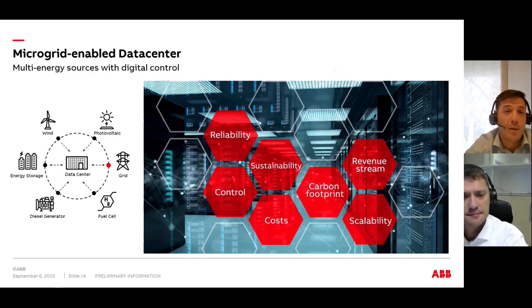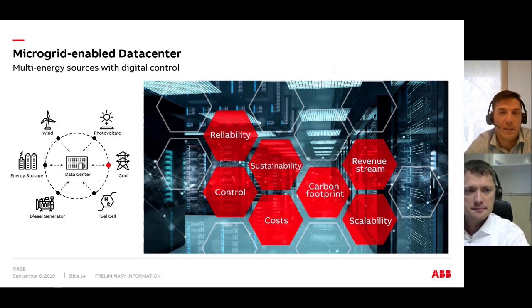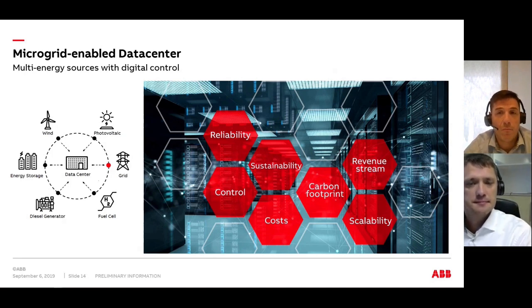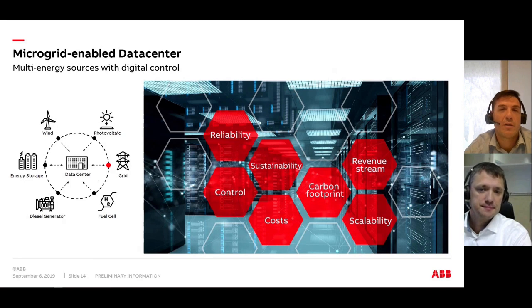This is not the target if we consider the previous point on sustainability. When we have a BESS in the microgrid, we have renewables. We can participate in different monetization schemes for additional revenue streams or even cost savings. These are possible due to the versatility of the microgrid for data centers, either by additional streams or by cost cutting. The return on investment of a microgrid-enabled data center can be readily realized. Grid services can be easily provided by just having a battery energy storage within the microgrid concept, in terms of reactive power support and fast frequency reserves. This is going to automatically enable an additional revenue stream to support the operations of the core business of the data center. Thank you, Carlos.